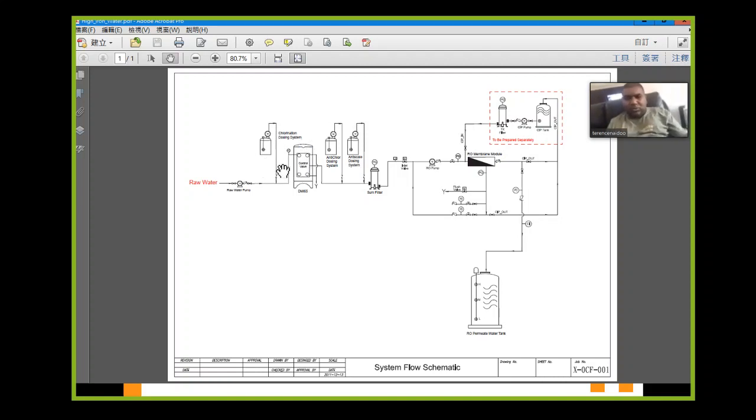In the morning, flush all the chlorine out. Then this is only one time. This is only required to be done at the initial startup. After that, you don't need to do that anymore. The media is already activated, because after that you will have chlorine dosing anyways continuously, but at a very low dosage rate. But if you don't do that, there's a chance that manganese can leak out. Manganese can block the membrane. Okay? Manganese looks black. So you must activate it.